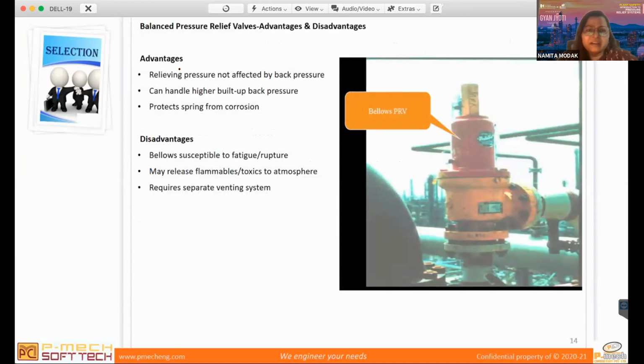So the advantage of this balanced bellows is that the relieving pressure is not affected by back pressure, which was affecting the conventional type. That was not the case in the balanced bellows. So when you are in doubt, like in initial sizing, when you really don't know the exact back pressure, it is always better to go with the balanced type, because it is not much affected and you have a lot of range, between a 30 to 50% ratio. So it's better to take a balanced bellows, though it is costlier than the conventional one, but you will always be in a safe position. It can handle higher built-up back pressure. It protects the spring from corrosion because this bellows can isolate your system.